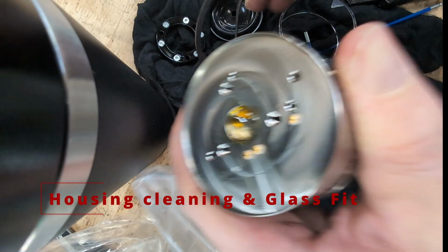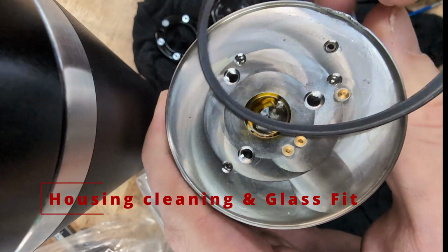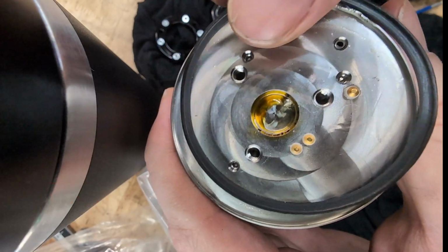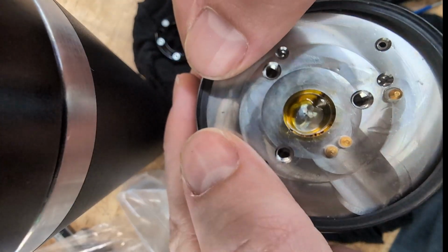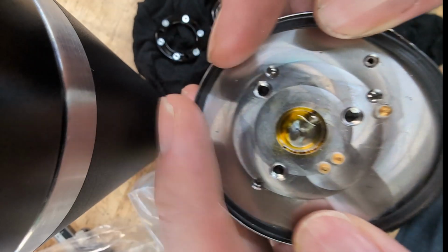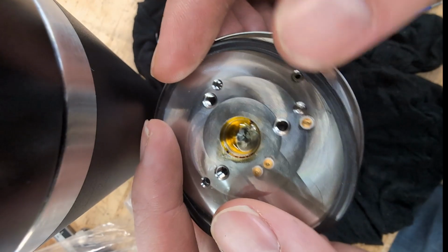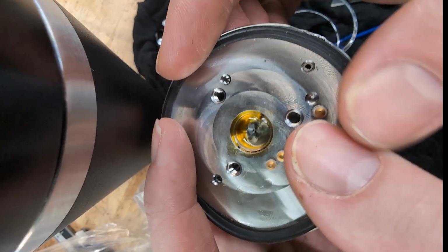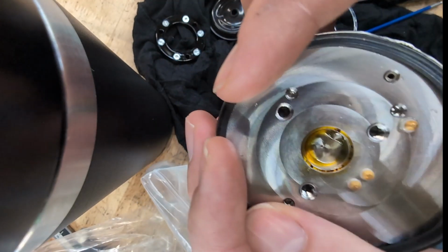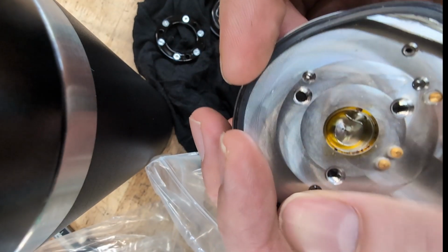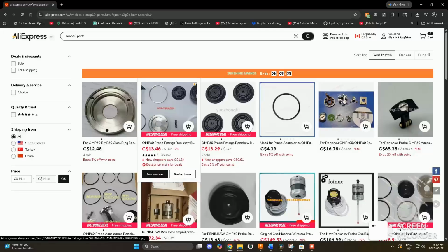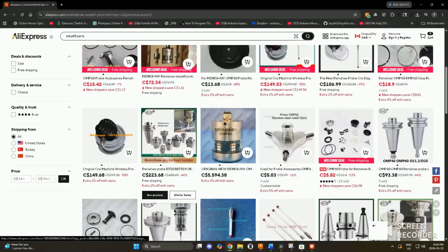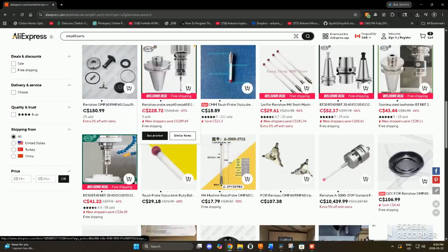Housing preparation and internal glass fit. My probe actually had some significant damage to the thin outer metal ring that contains the glass. Before filming, I had to very gently form that metal back into place so everything would sit correctly. It doesn't have to be visually perfect. The replacement glass actually has a bit of clearance around the ring, so if it isn't binding or pinching, you're fine. You can find nearly every component for these probes online, including the electronics.